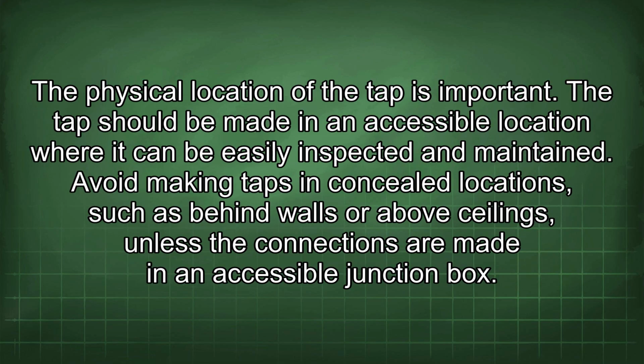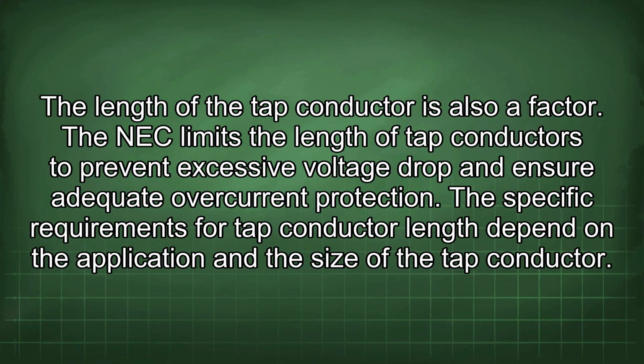The physical location of the tap is important. A tap should be made in an accessible location where it can be easily inspected and maintained. Avoid making taps in concealed locations, such as behind walls or above ceilings, unless the connections are made in an accessible junction box. The length of the tap conductor is also a factor. The NEC limits the length of tap conductors to prevent excessive voltage drop and ensure adequate overcurrent protection. The specific requirements for tap conductor length depend on the application and the size of the tap conductor.